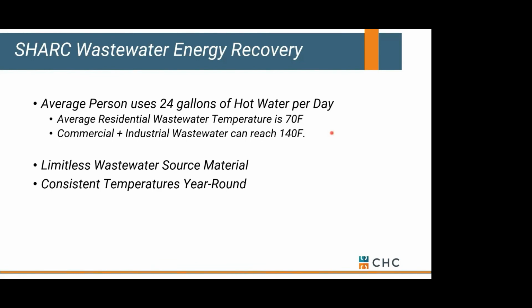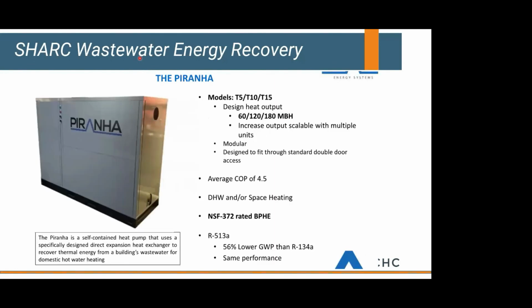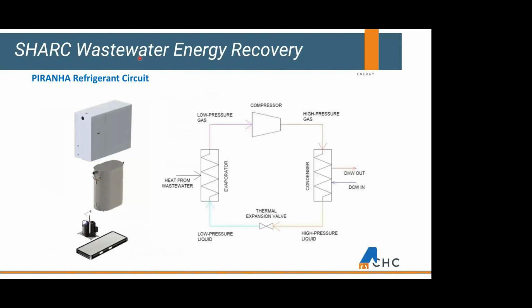If you want to look at something interesting, that might be using that same refrigerant cycle to pull some heat for domestic hot water out of wastewater, believe it or not. There's a technology out there right now that lets you do that. And they are simply using that refrigerant cycle, and they're using waste heat off of our sanitary or sewer that's leaving a building to generate domestic hot water. You're like, oh, gross. But they've got a heat exchanger over here that they're going to fill with sewage. There's no contact. It's simply, I want to say, helping or assisting with the refrigeration cycle.